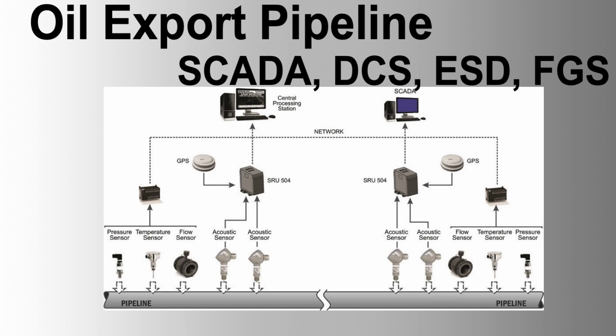Operating system: Windows Server 2019 for servers, Windows 10 for operator workstations. Database: SQL Server for data logging and historical archiving. HMI development: FactoryTalk View Studio for creating graphical interfaces and control screens. Alarm management: real-time and historical alarm handling with customizable alarm priorities and notifications. Historical data: data logging at 1-second intervals with up to 5 years of historical data storage.